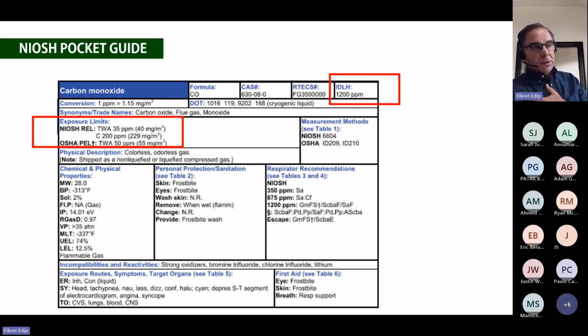Therefore, as a gas detection system manufacturer, we set our high alarm level for CO at 100 ppm. In some jurisdictions, they go even more conservative. They go to 75 ppm. So imagine that at 100 ppm, we're giving you a high alarm. We start activating the fastest speed of the fan to purge the contaminant from the building envelope. We will never let it reach that high, okay?